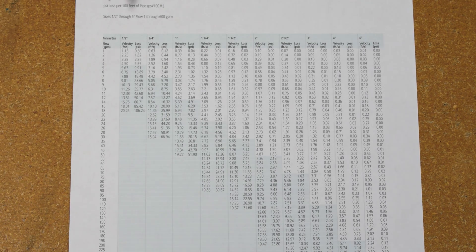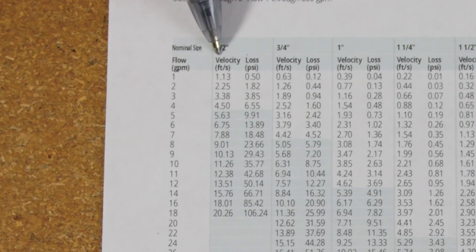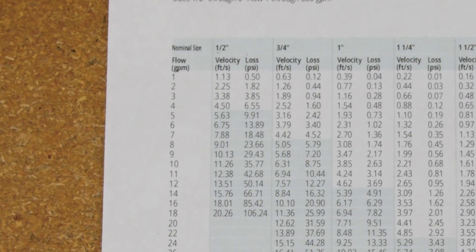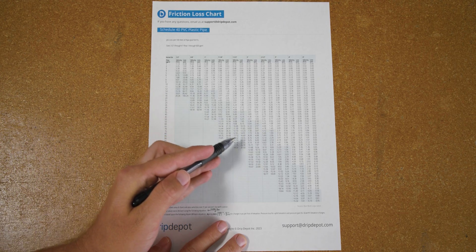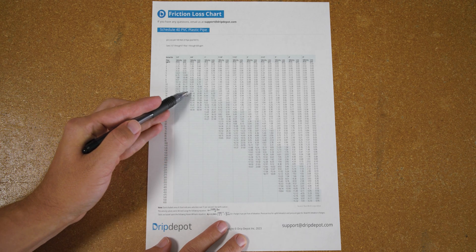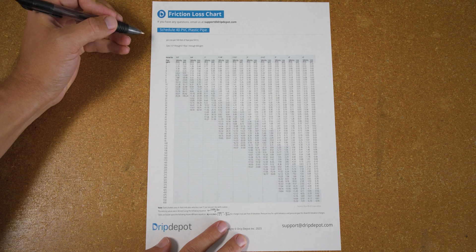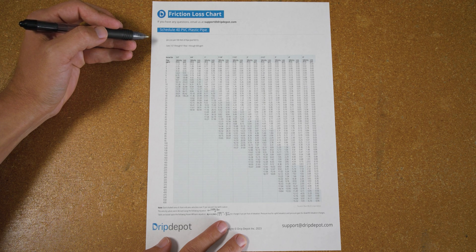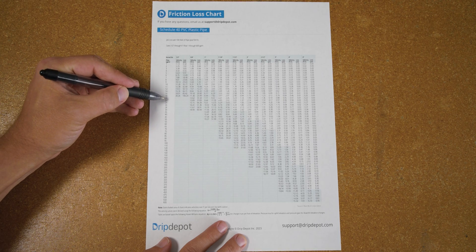The columns on the chart give us two important pieces of data for each diameter of pipe: the pressure loss in pounds per square inch for every 100 feet of pipe, and the velocity of the water in that diameter of pipe based on the flow rate in gallons per minute. What makes it even easier to read is that velocities over five feet per second are shaded, meaning that the diameter of the pipe is too small for the indicated flow rate. To calculate the friction loss, all you have to do is add the number for every 100 feet of pipe.